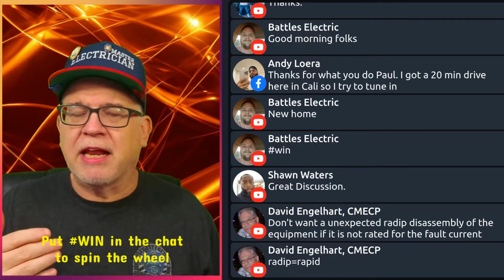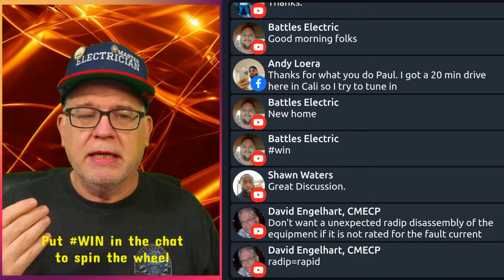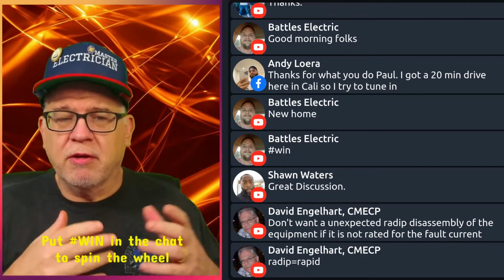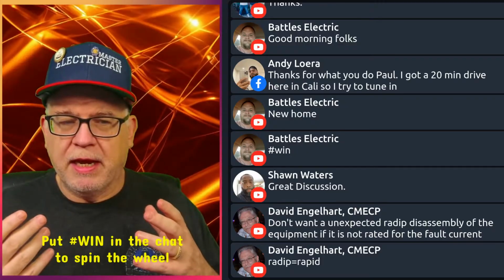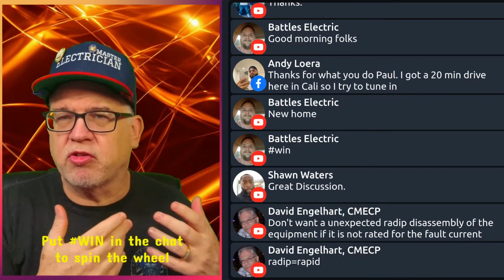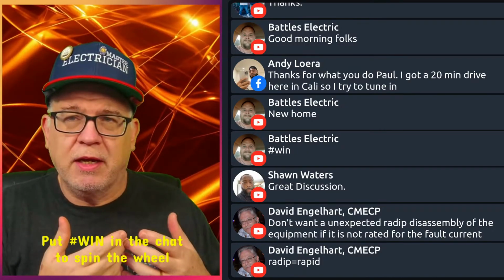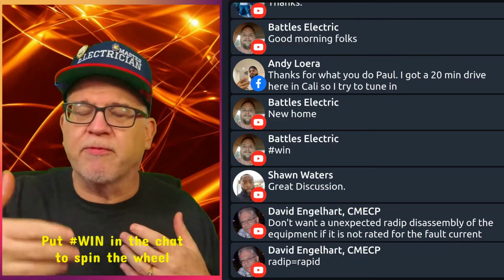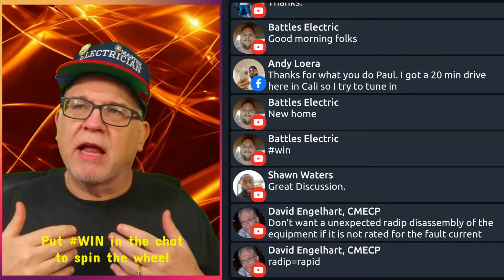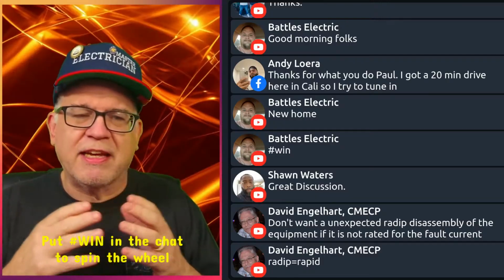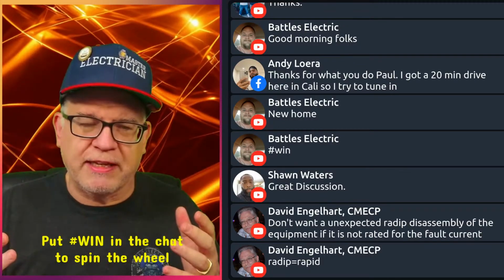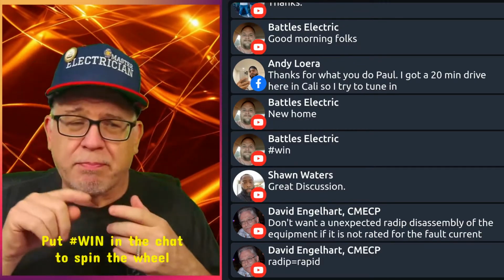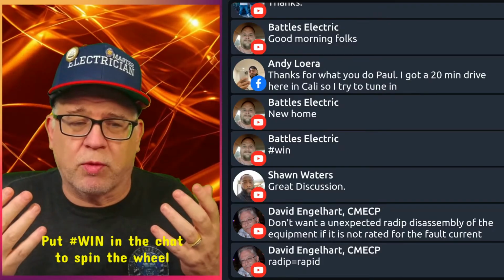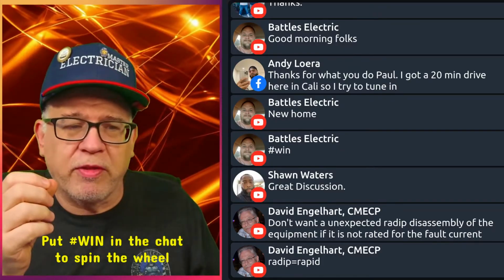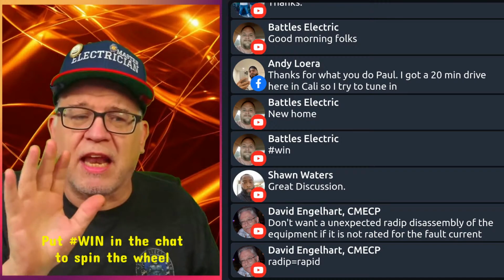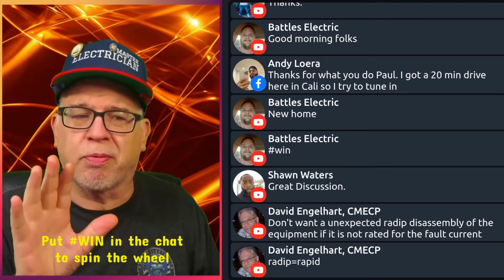But look, you've got to lighten up if you're doing reviews. If it's 35,000 rating at the service equipment and the utility tells you that it's 22,000 coming in, and you start demanding a value on different things downstream, well, obviously it can be calculated out. You've got to know the different lengths of conductors. You just plug it into software; Cooper Bussmann has one. But I always tell the people reviewing this, you need to lighten up a little bit. Don't take your job so proudly.